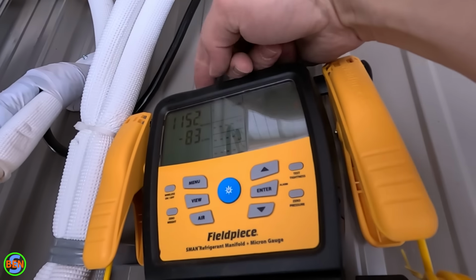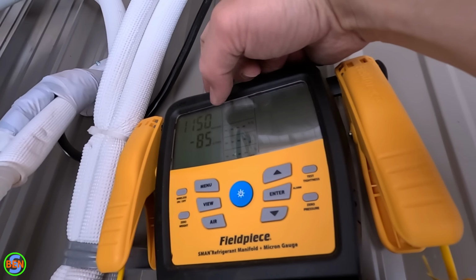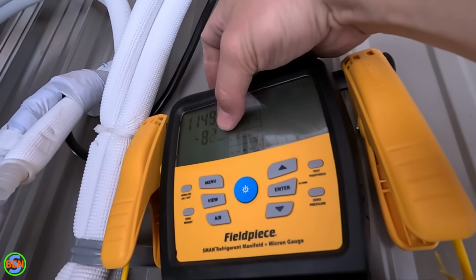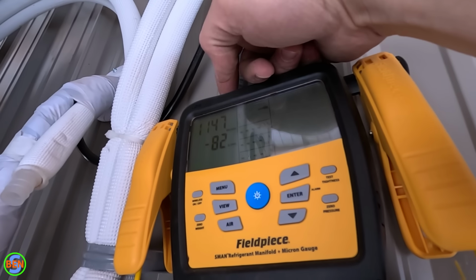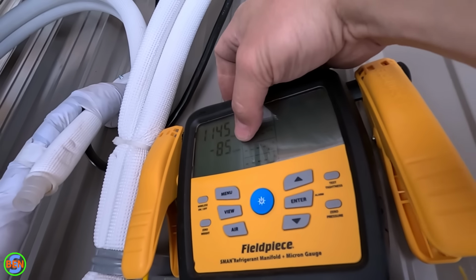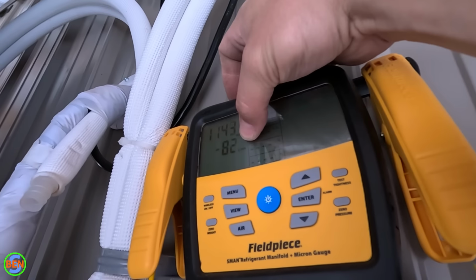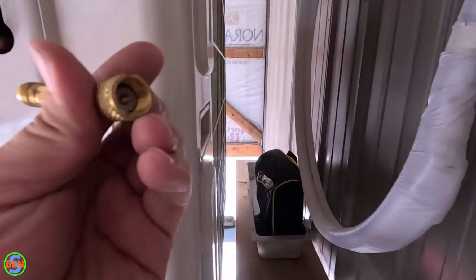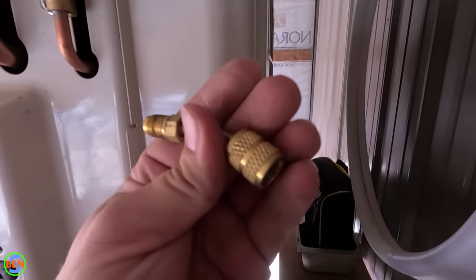We can pull them all together, but refer to the installation instructions because your unit may be different. You may have to pull a separate vacuum on each set of lines versus being able to pull the vacuum on the entire thing. If you have a standard set of gauges, you're probably going to need to purchase an adapter to these mini splits. They do not use the standard 1/4 inch flare style connection for accessing the system, so I will link to those adapters in the description below.